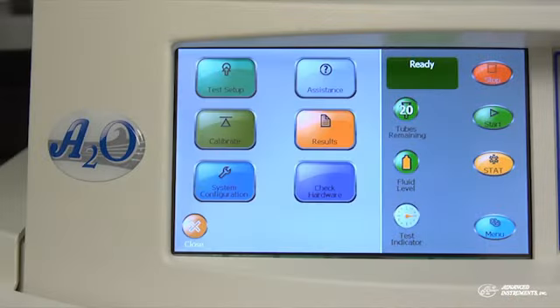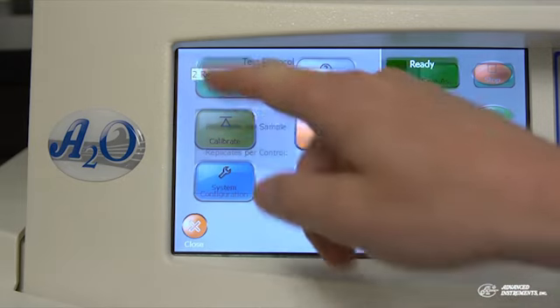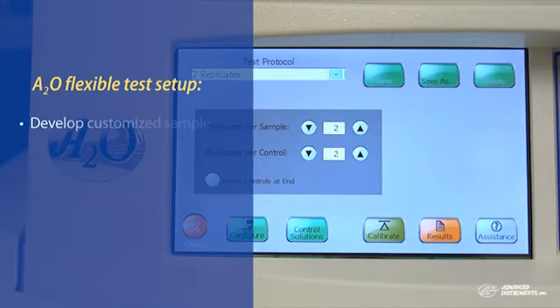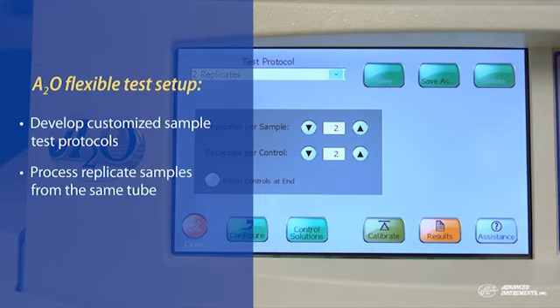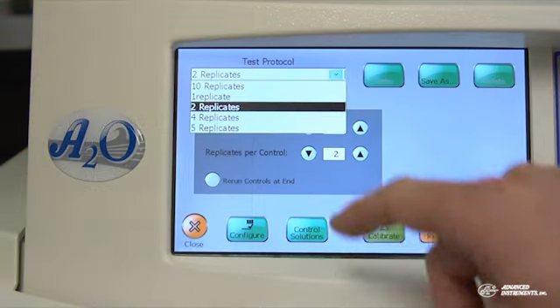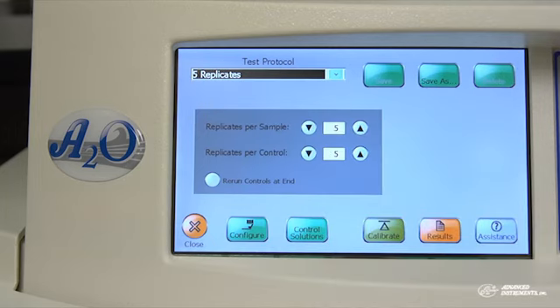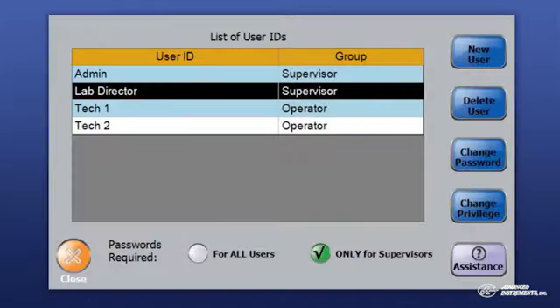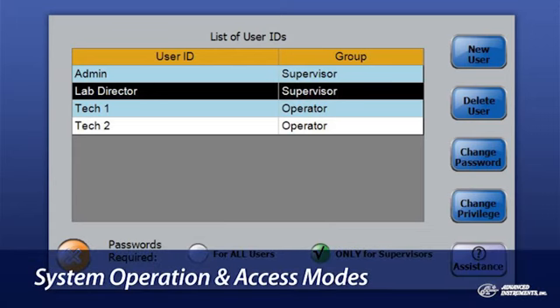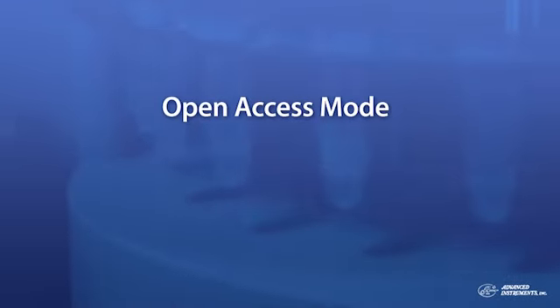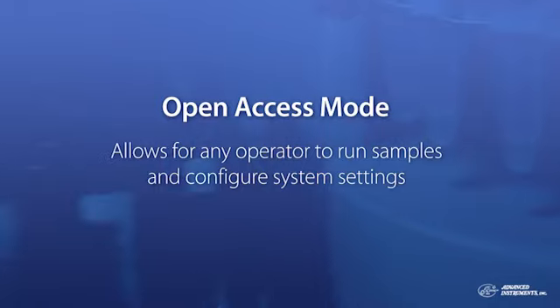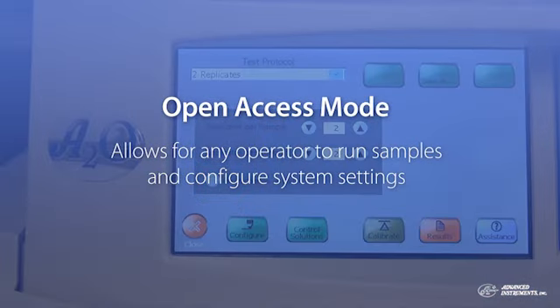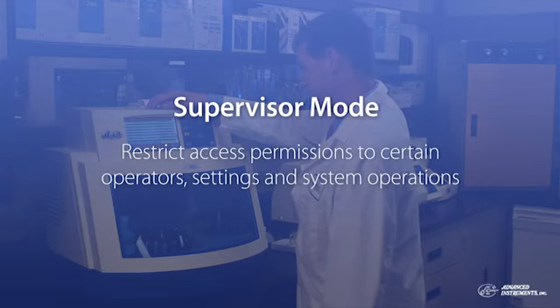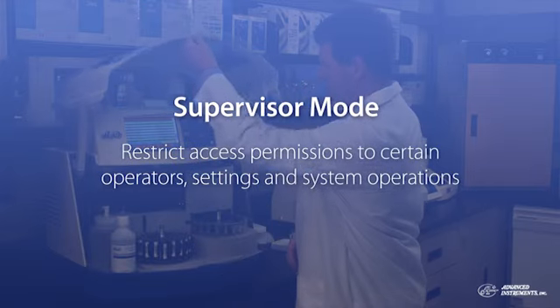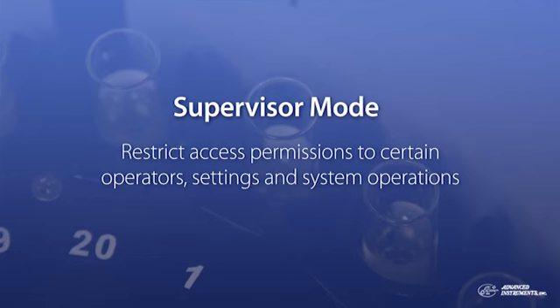The flexible test setup features of the A2O provide the ability to develop customized sample testing protocols specific to your laboratory or test method. Replicate samples can be processed from the same sample tube for ease of use. A2O system operation and access can be configured a variety of different ways, depending on the needs of your laboratory. Open Access Mode allows for any operator to run samples and configure system settings. A Supervisor mode is available that can restrict access permissions to certain operators, settings, and system operations.